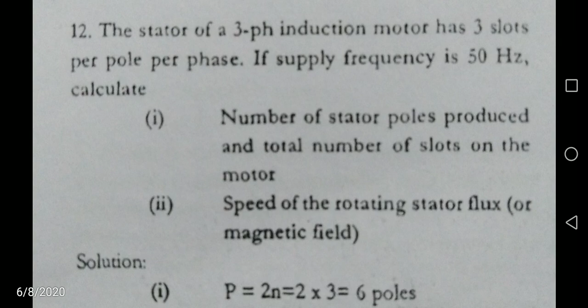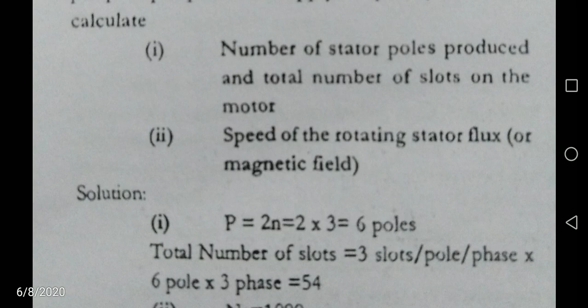The number of poles equals 2 into N, where N is the slots per pole per phase, which is 3. So the number of poles equals 6 poles. Total number of slots equals 3 into slots per pole per phase, so 6 into 3 into 3, that is 54 slots.